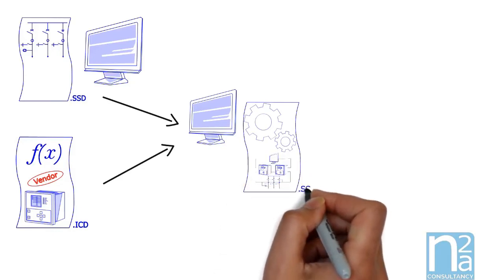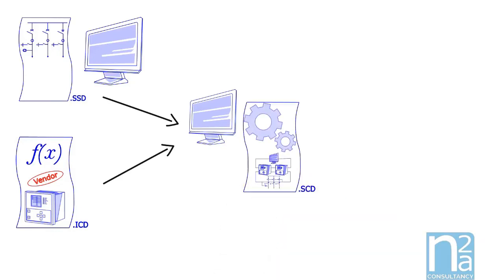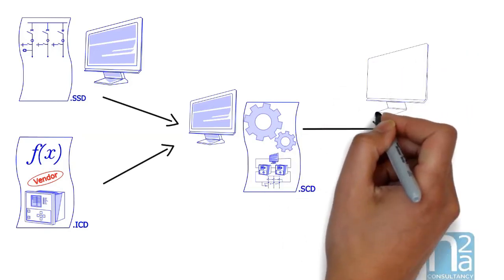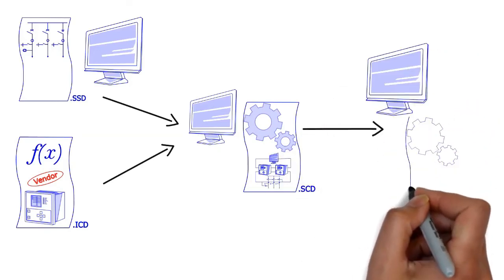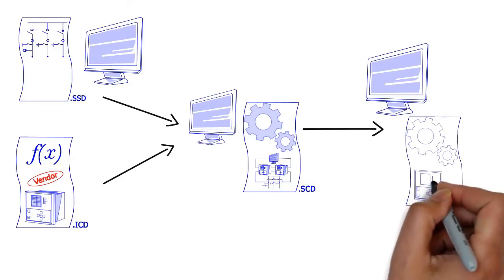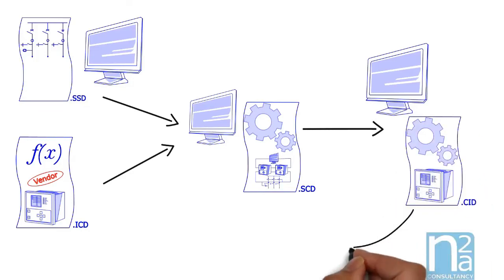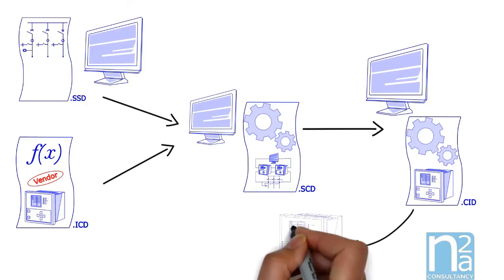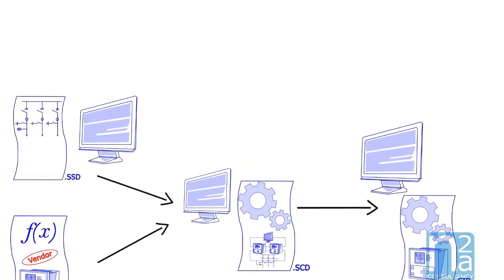These two files are used in a system configurator to create a new file which is called SCD, Substation Configuration Description. During this configuration phase, all interlocks between IEDs are also defined. The last phase consists to extract from this SCD file individual configuration IED descriptions, which is called CID file. This file could be then transferred to IEDs to set automatically their configuration. Even if this looks simple, multiple possibilities make this phase quite complex, and standardization of solutions is highly recommended.